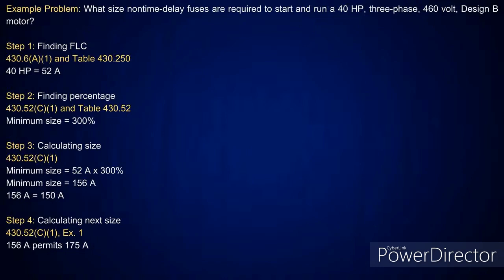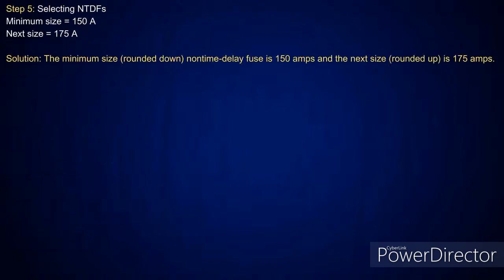It said in 430.52(C)(1), I can't exceed the calculated value. So I drop down to the next standard size, which is 150 amp. Now, if they ask you for the next size, I can look at exception one. Exception one tells me I can go up to the next standard size, which is 175 amp overcurrent device. Okay? So that's how you size right there.